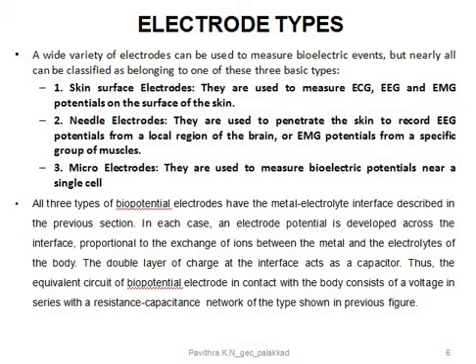All three types of biopotential electrodes have the same equivalent circuit. In each case the electrode potential is developed across the interface and it is proportional to the exchange of ions between the metal and electrolytes of the body. There is a double layer of charge at the interface which acts as a capacitor. Thus the equivalent circuit of this electrode consists of a voltage in series with a resistance-capacitance network.